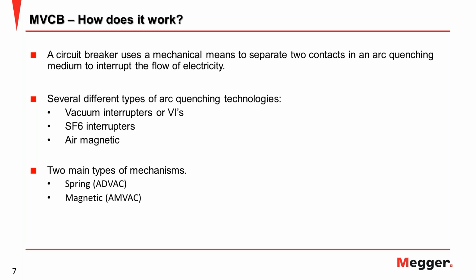Okay, now how does it work? Actually, almost all breakers have the same principle. The circuit breaker uses a mechanical means to separate two contacts in an arc quenching medium to interrupt the flow of electricity. The arc quenching medium of the breaker uses different technologies. There are several types like vacuum interrupter, SF6 interrupter, or air magnetic, and also air or anything else used for arc quenching. It can affect the type of the breaker.